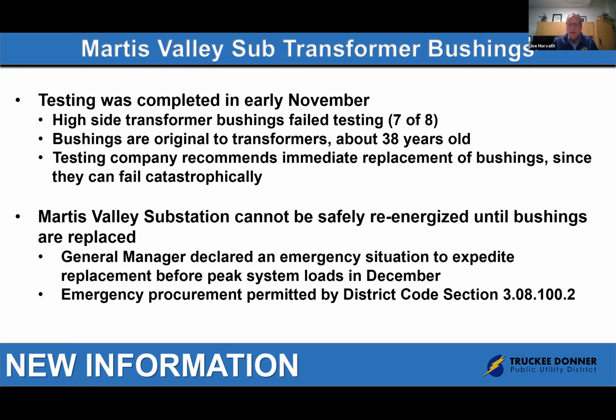The testing was completed by NCPS in early November, and the substation passed very well in the different categories, except that the high side transformer bushings failed testing. 7 out of 8 bushings tested failed the testing.